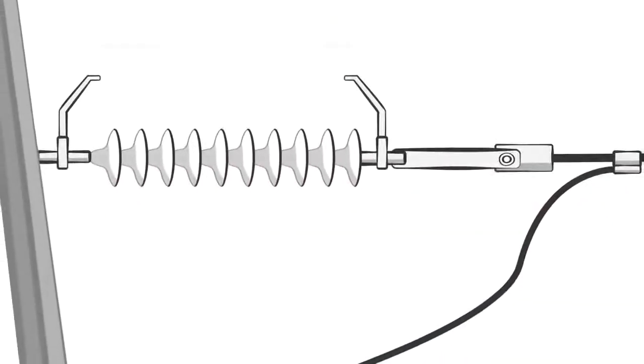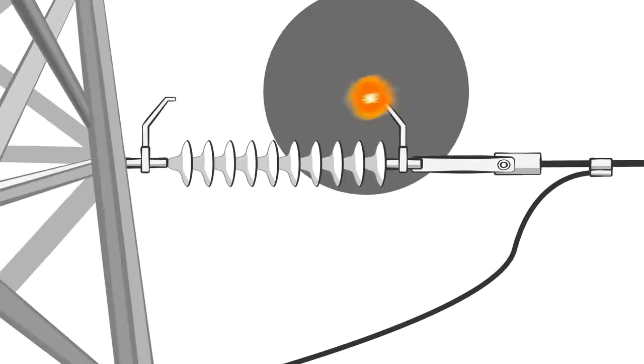Another common discharge type is the corona discharge. This discharge typically occurs around sharp corners or discontinuities on the surface of an object. Corona discharges are usually not problematic, but they may damage nearby materials or insulators.